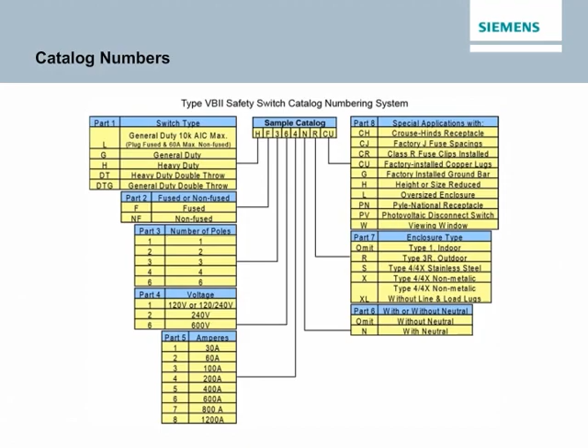It's a heavy-duty switch type, it's fused, has 3 poles, has a voltage rating of 600 volts, has an amp rating of 200 amps with a neutral, it's a Type 3R enclosure, and it has a special application of factory installed copper lugs.